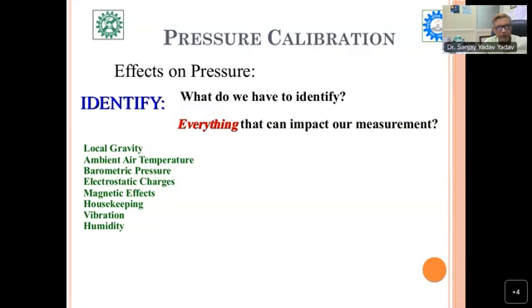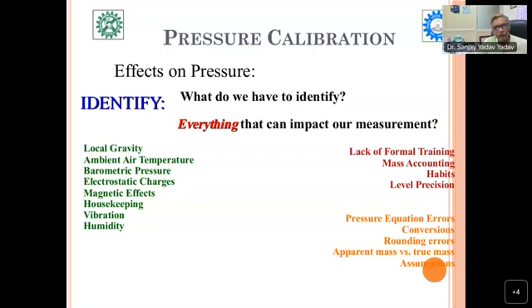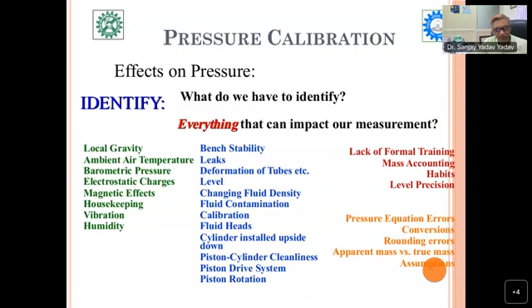Then the second one is characteristics related to bench stability. These are the bench level requirements: bench stability, leak in the system, deformation of tube. If there is severe deformation of the tube, it will affect the level of precision, level of the instrument, changing fluid density, fluid contamination. When you are connecting a customer gauge, a different fluid in your customer gauge and a different fluid in your standard will cause contamination. Calibration procedure, fluid head corrections, cylindrical piston installed, piston cleanliness, piston drive, and piston rotation.